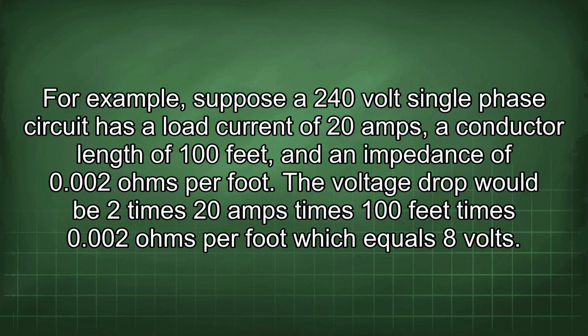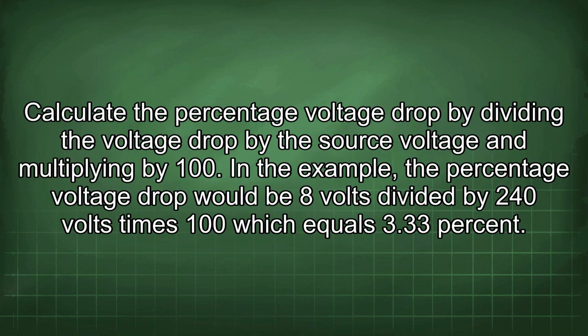For example, suppose a 240 volt single-phase circuit has a load current of 20 amps, a conductor length of 100 feet, and an impedance of 0.002 ohms per foot. The voltage drop would be 2 times 20 amps times 100 feet times 0.002 ohms per foot, which equals 8 volts. Calculate the percentage voltage drop by dividing the voltage drop by the source voltage and multiplying by 100. In the example, the percentage voltage drop would be 8 volts divided by 240 volts times 100, which equals 3.33%.